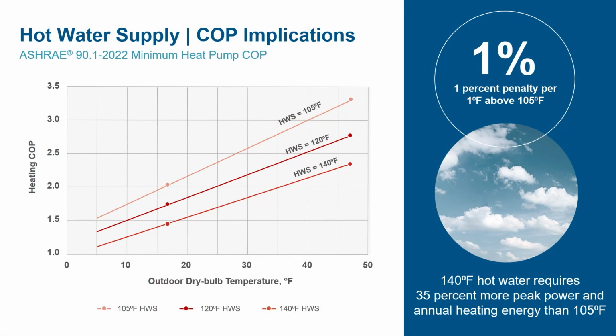This brings us to why reduced fluid temperature is beneficial. Shown in the graph are ASHRAE 90.1 minimum COPs for air-to-water heat pumps for heating. When looking at minimum efficiencies for the same equipment, delivering 105-degree Fahrenheit fluid is 35% more efficient than delivering 140-degree supply fluid. Simply put, the lower the fluid temperature delivered, the less energy consumed. As more buildings move to electric sources for heat, a larger percent of the overall grid demand will come from space heating. This is where designers have an opportunity to make a large impact.